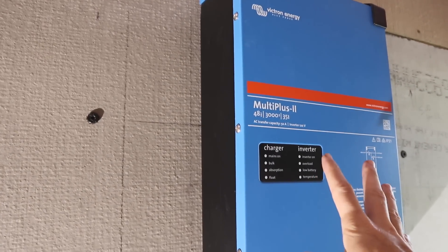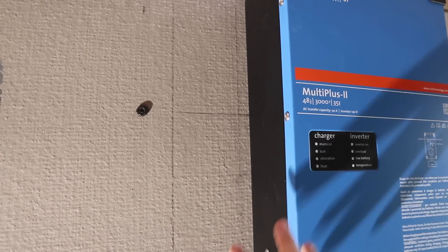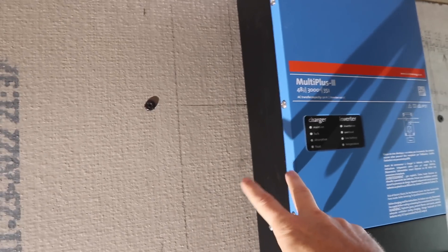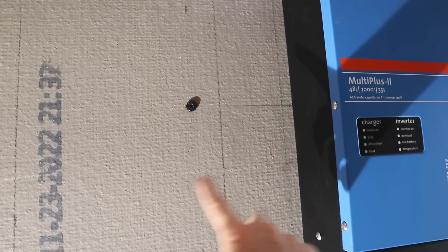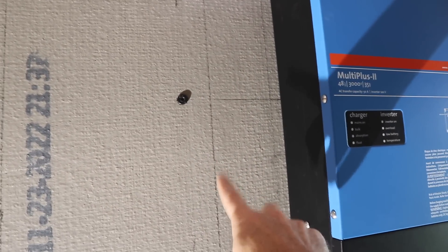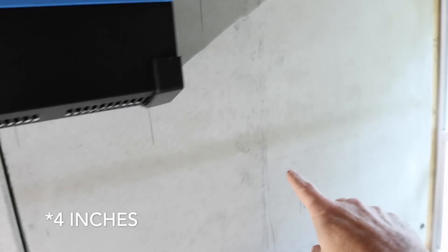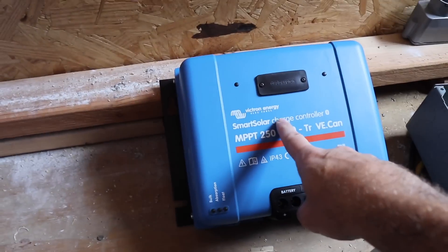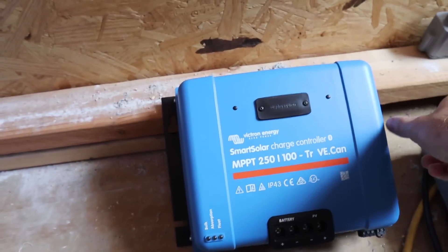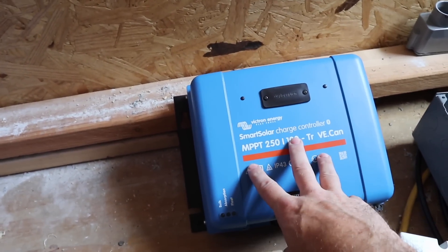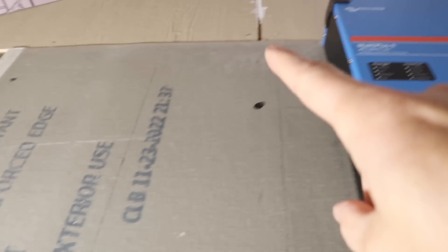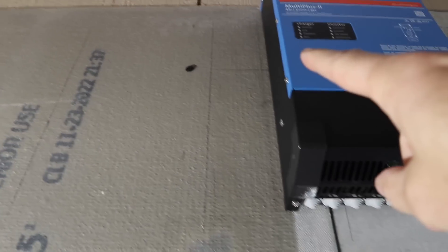What's really nice about these Victron products is that you can mount them closer together than most. So the spacing on these between the two multi plus inverters is only 10 centimeters. Also where we are going to put the MPPT, which is right down here, we only need 10 centimeters around each side to mount this.